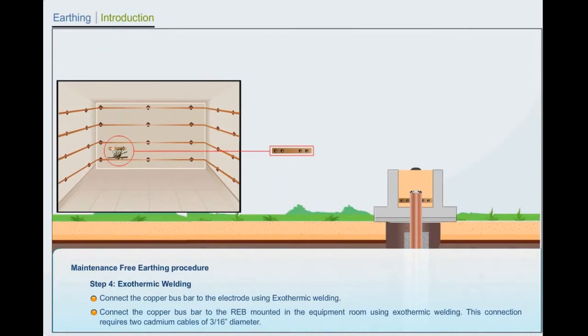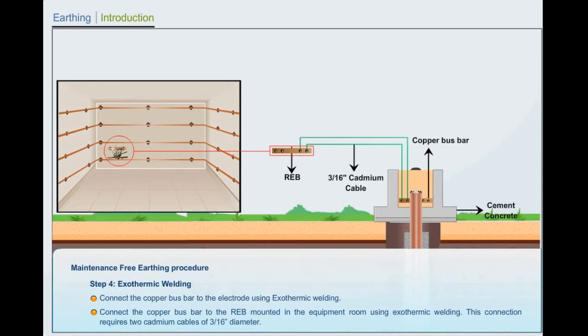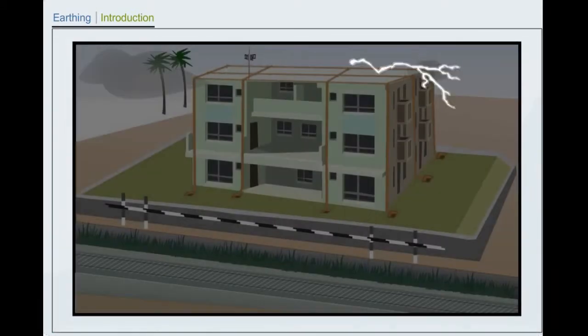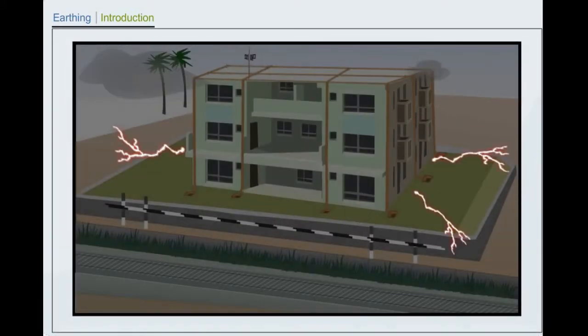Connect the copper bus bar to the room earth bar mounted in the equipment room using exothermic welding. This connection requires 2 cadmium cables of 3/16 inch diameter. Due to lightning, a very large amount of current will be dispersed through the ground in all directions and will result in different ground potentials. To achieve equipotential bonding to protect the equipment from the damages due to different ground potentials, perimeter earthing is required.